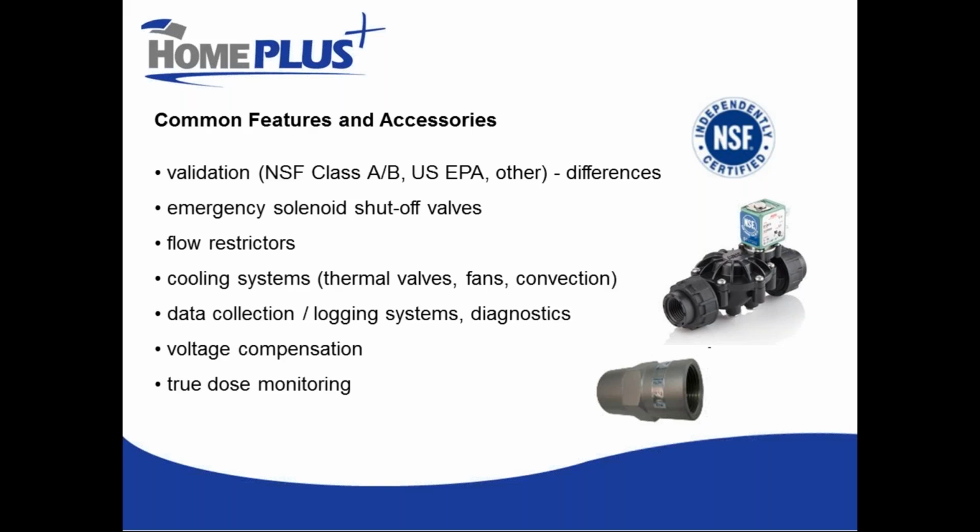And I would actually argue in most cases that that would be preferred for a number of reasons. You get some additional redundancy. You know, if one unit is down, at least you have some water being treated. And quite honestly, multiple NSF 55 Class A units are often cheaper than one larger US EPA validated unit.